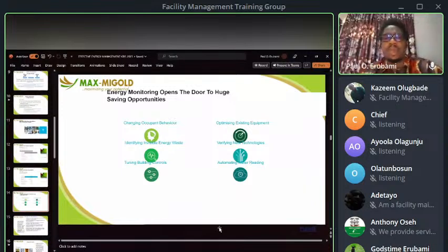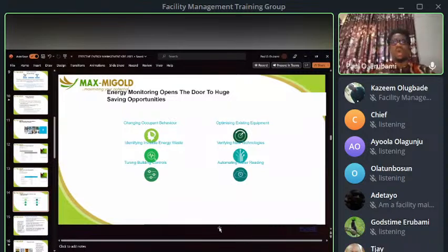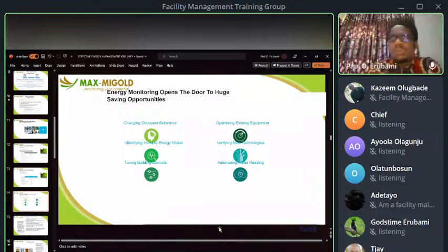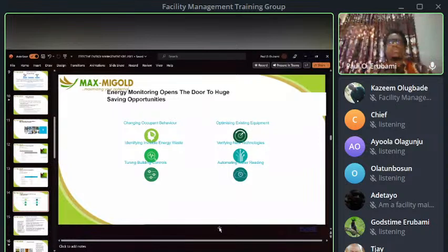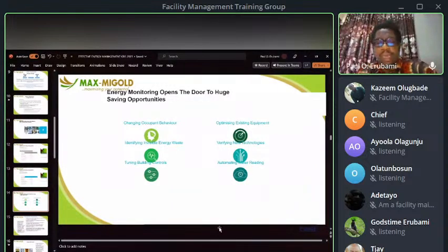So optimizing your existing equipment, verifying new technologies. Whenever you're going to switch from fluorescent or halogen, for example, to LED lights, you need a means of monitoring that circuit, so you can say this is what it was reading or consuming before I switched, not just using the nameplate rating to make those calculations. You cannot make those calculations from looking at the nameplate ratings.